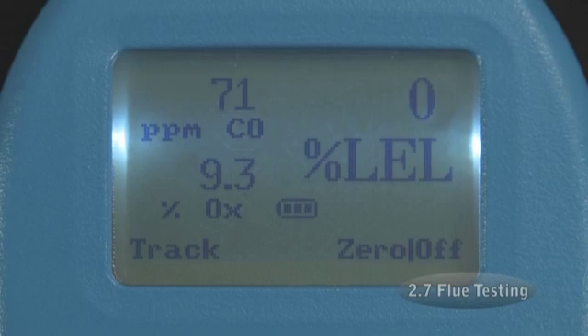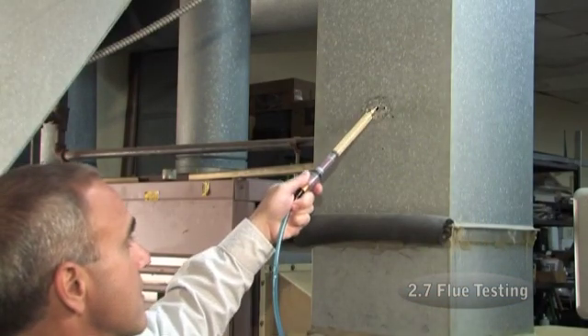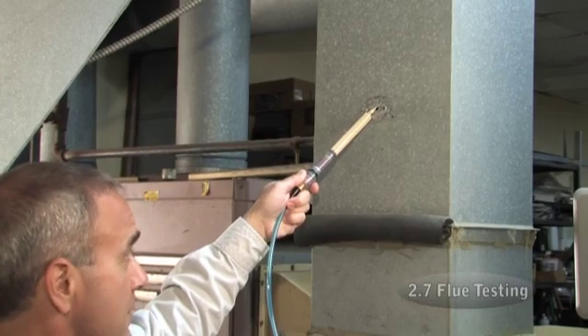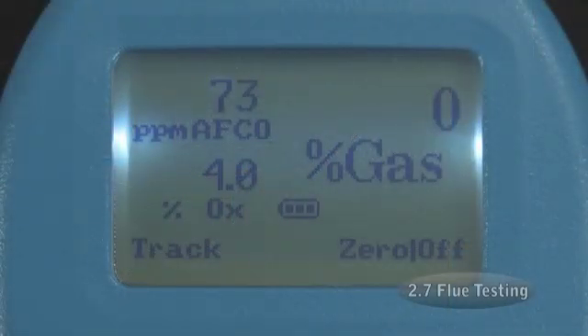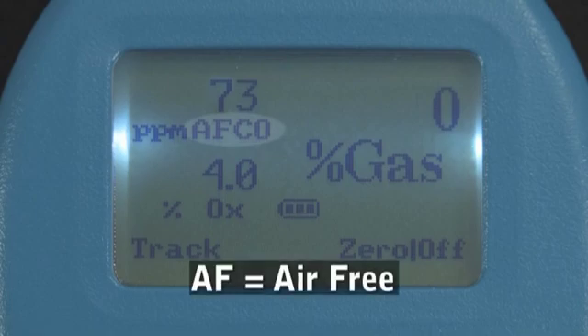Air-free CO is the AGA's recommended way to check appliances in flues. If you need to do air-free CO readings, you have to be equipped with both CO and oxygen sensors. The Explorer does the conversion to air-free CO automatically. Instead of showing ppm CO, the display will show AFCO, meaning air-free. CO measurements on an air-free basis will be higher than ordinary CO measurements. For example, if the oxygen level in the flue gas is 10%, the air-free CO reading would be approximately twice the measured value.